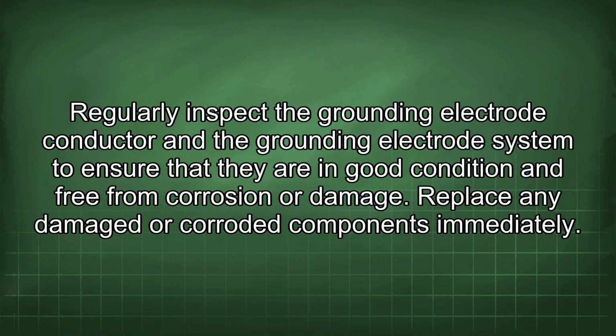Regularly inspect the grounding electrode conductor and the grounding electrode system to ensure that they are in good condition and free from corrosion or damage. Replace any damaged or corroded components immediately.